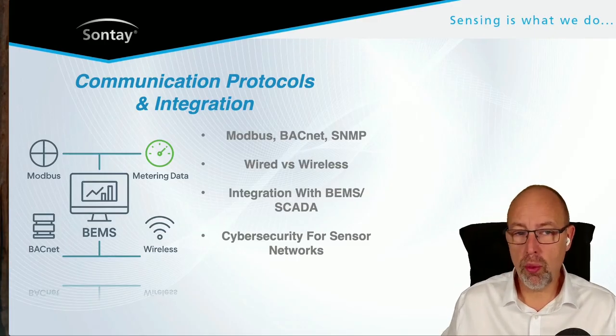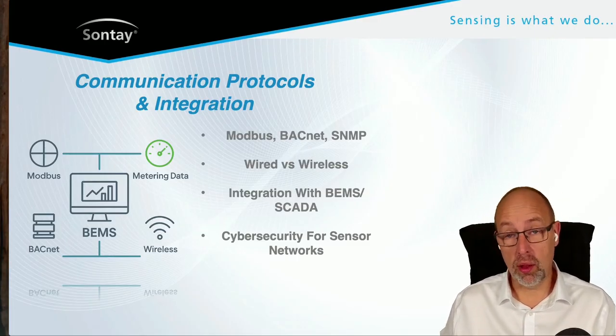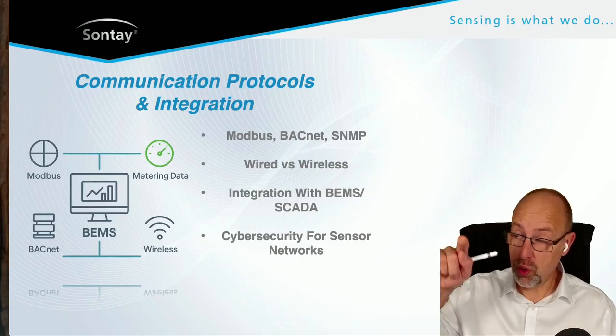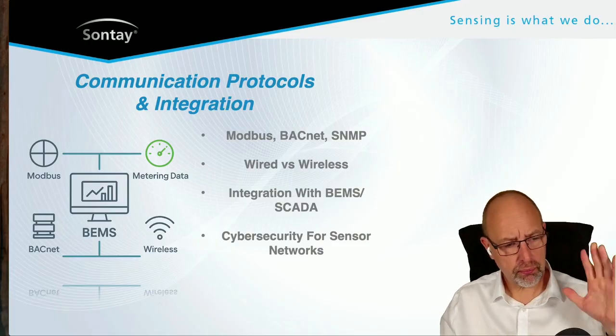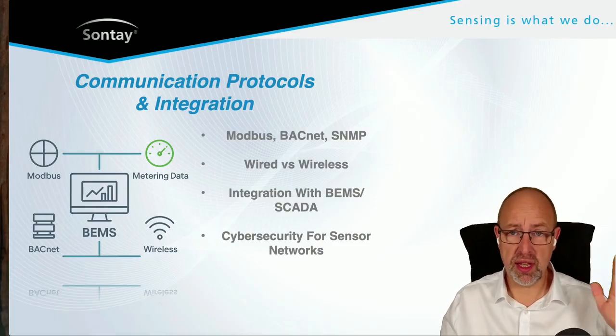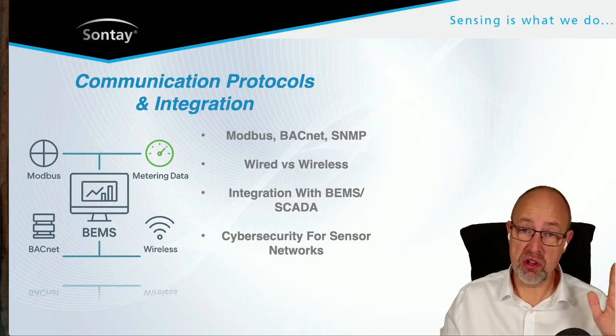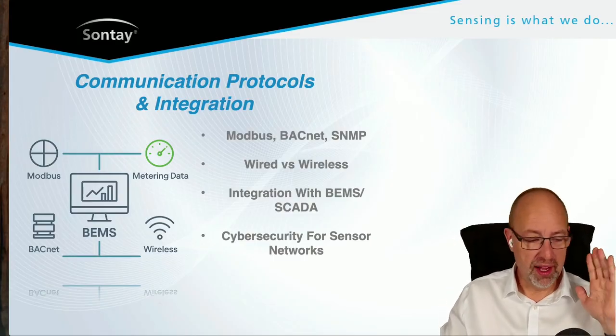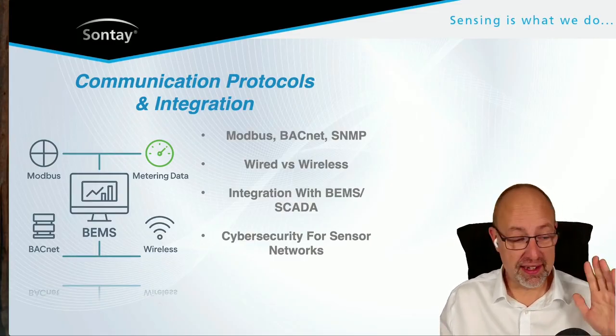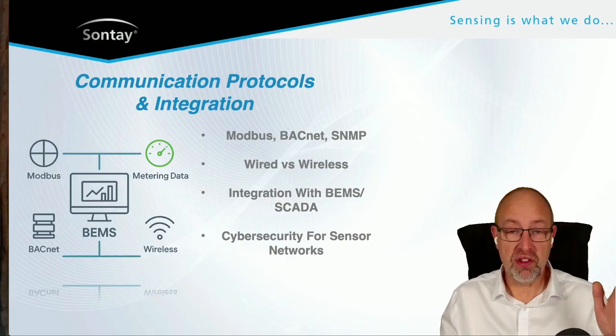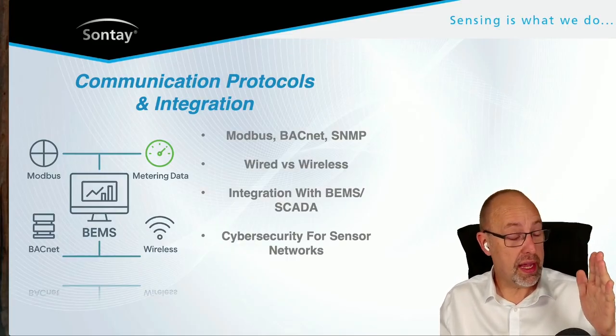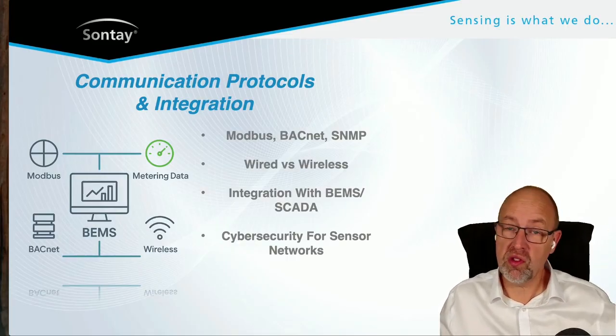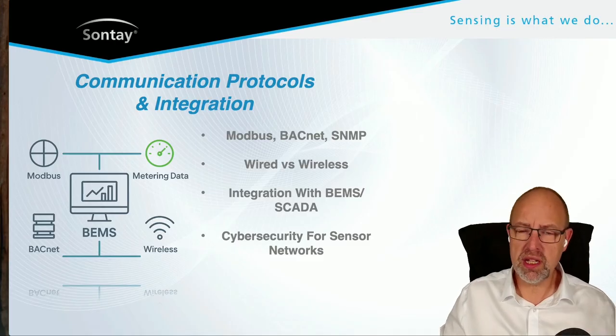But there are drawbacks to using smart sensors as well. You daisy chain them together, so you connect all those sensors together. If something happens, if someone snips a cable, then usually if they're in a data center and they've cut a cable, that's probably the last thing they'll ever do in that data center. But if it happened, then all of the sensors after that would go offline. So it's not without its problems.